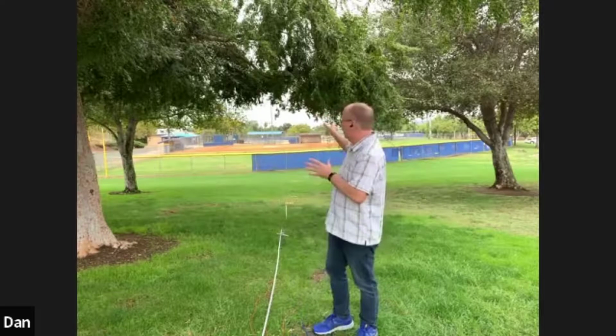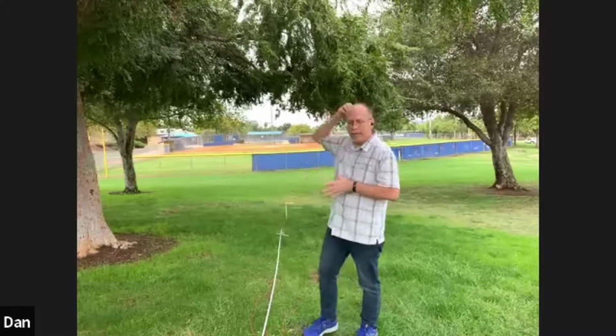The other thing that makes a difference is irrigating this area. Irrigation affects how you drive the probe in, because if it's dry and you have to hammer it, it's hard on the equipment and creates air pockets. Air is insulating, so moisture has an influence. Technically, you should do this test periodically, probably on an annual basis. It's only required once for warranty, but regular testing is good, and that would drive your moisture checks.